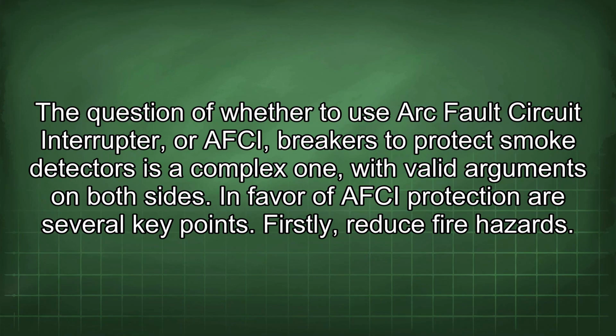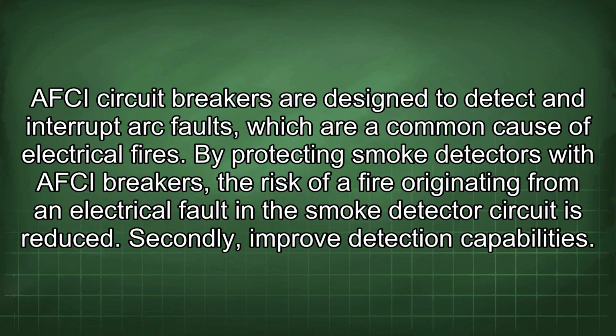The question of whether to use arc fault circuit interrupter, or AFCI, breakers to protect smoke detectors is a complex one, with valid arguments on both sides. In favor of AFCI protection are several key points. Firstly, reduced fire hazards. AFCI circuit breakers are designed to detect and interrupt arc faults, which are a common cause of electrical fires. By protecting smoke detectors with AFCI breakers, the risk of a fire originating from an electrical fault in the smoke detector circuit is reduced.